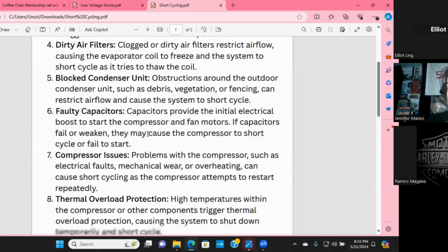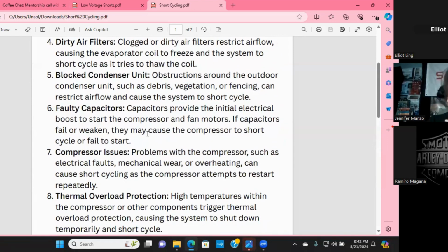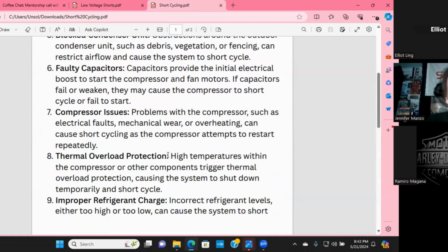Faulty capacitors. We were just talking about this with Ramiro. A lot of the time it's a bad capacitor, you guys. So what happens is you need the correct amount of airflow in order to not short cycle. If you're not getting the correct amount of airflow because your fan, even though it's running, is not running correctly, it's not running at the designed load, you're ending up with overamping or you're ending up with not enough capacitance to run the fans correctly. They'll slow down or they'll run backwards. Lots of things happen from this problem.